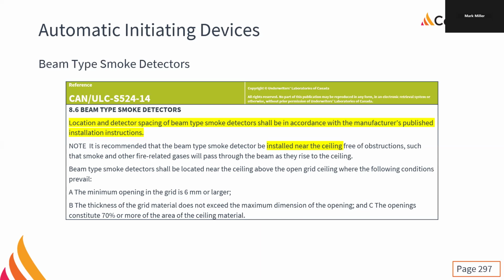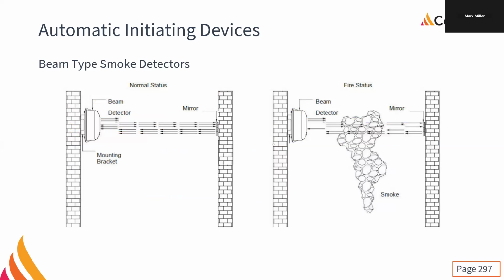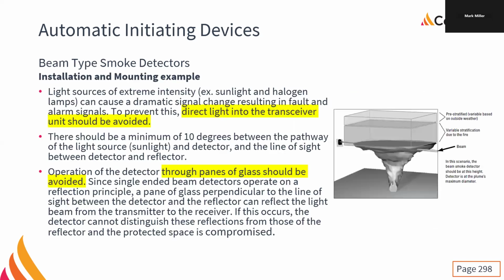This is one of the things where you absolutely need to have the shop drawings on these things before you start roughing in. You know how many wires and where. Some of them have base units that get installed down at floor level for aiming and control and maintenance. Some of them don't. They are all completely different. I have not yet installed two identical beam detectors. I've installed six jobs with beam detectors, multiples on jobs, so at this point I've installed six different models. Every time I get them, they're different. So you've got to really make sure that you know what you're doing. Otherwise, you can have some pretty extreme troubles.